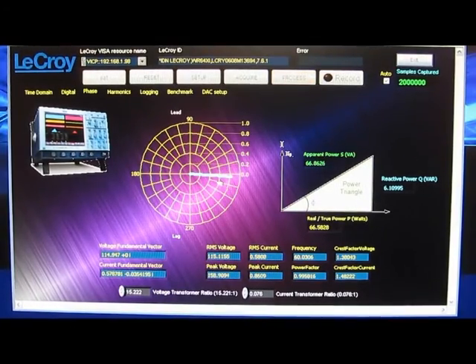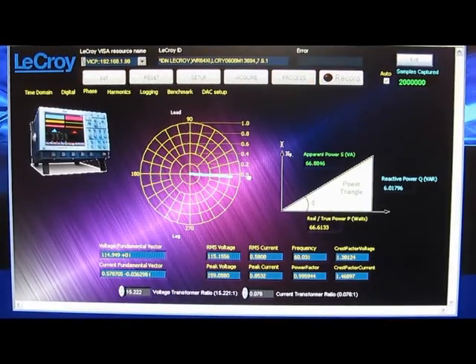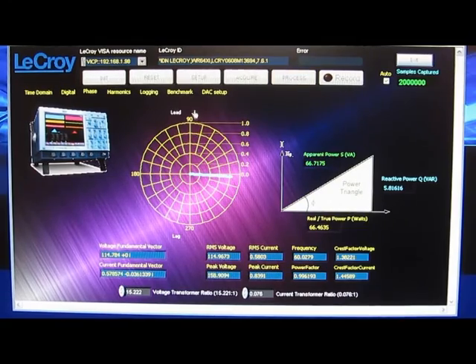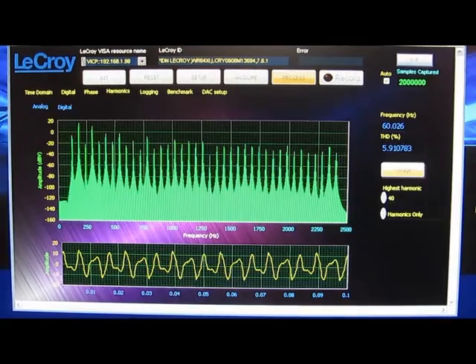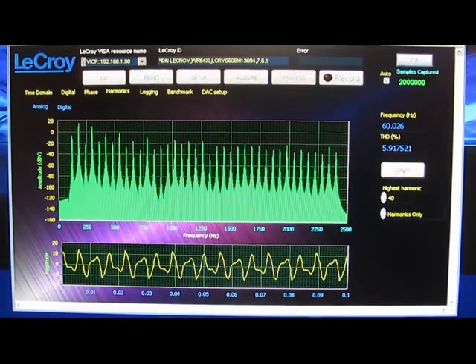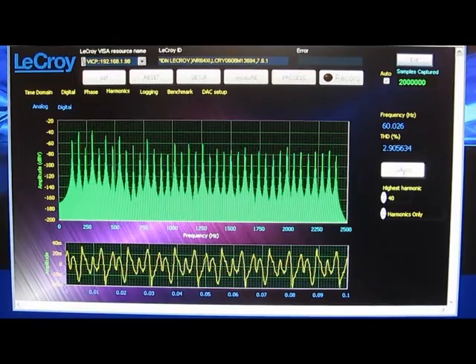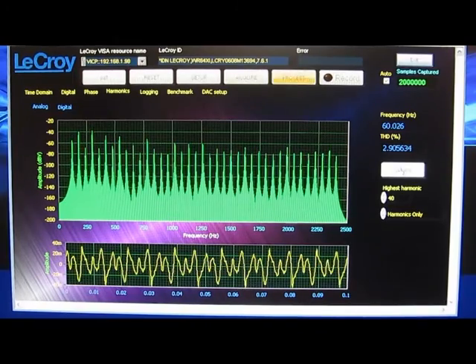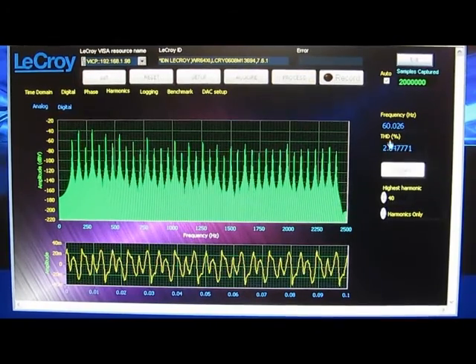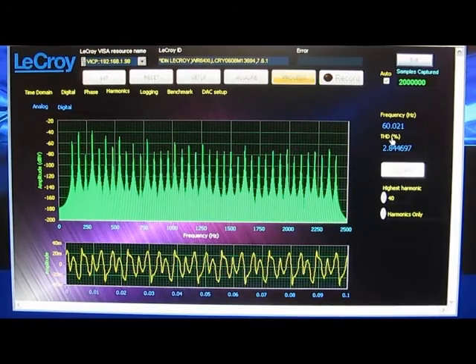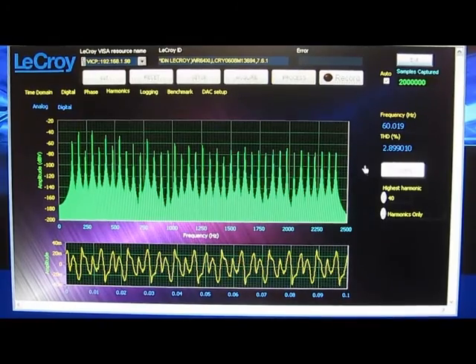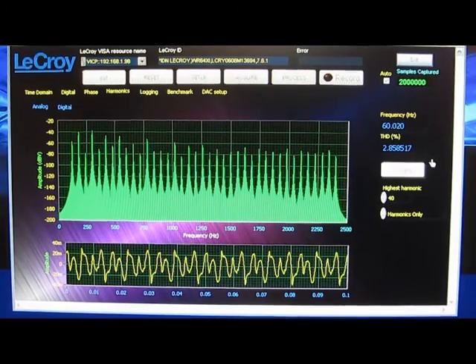Looking at the phase plot again, we can see that we're roughly at 0 degrees. Here we're looking at the voltage harmonics. This selects the current harmonics. The THD for the current is roughly 2.9%.